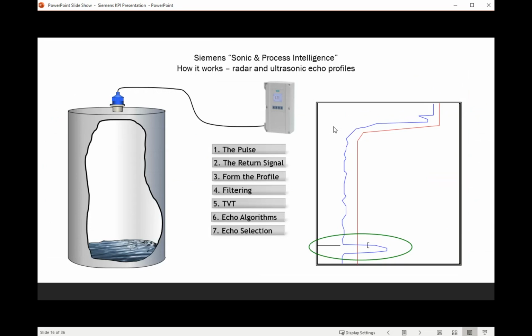After that, it applies some filtering, a spike filter and a narrow echo filter, to take out some of the noise. Then it forms the TVT, the time varying threshold. That's the red line on the chart over on the right. What the TVT does is help select out areas where you may be getting false reflections or some noise. Essentially any echoes that extend to the right of the TVT line in this picture could be considered valid echoes. You can see in this particular example there's only one valid echo.